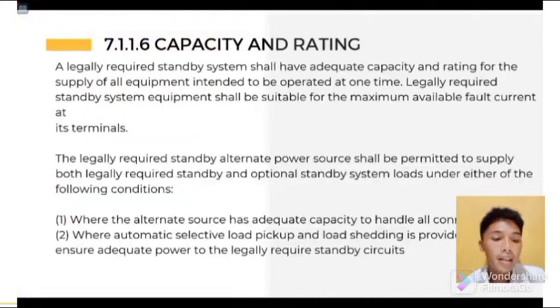Capacity and rating. A legally required standby system shall have adequate capacity and rating for the supply of all equipment intended to be operated at one time. Legally required standby system equipment shall be suitable for the maximum available fault current at its terminals. The legally required standby alternate power source shall be permitted to supply both legally required standby and optional standby systems loads under either of the following conditions. The first condition is where the alternate source has adequate capacity to handle all the connected loads. Second condition, where automatic selective load pickup and load shedding is provided that will ensure adequate power to the legally required standby circuits.